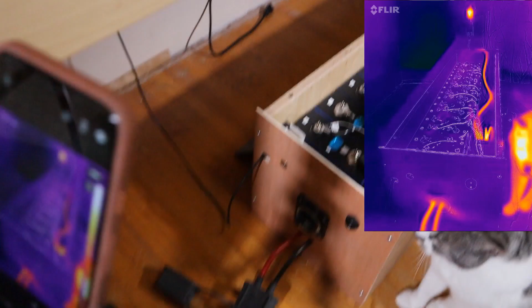Absolutely nothing. Absolutely nothing on the flexible bus bars. So as far as I'm concerned, this settles it: flexible bus bars are better than rigid. If only because, as you saw with the rigid bus bars, there were a couple of hot spots. I'm assuming because the metal plate wasn't sitting properly on top of the bus terminal, generating a little bit of heat. With the flexible bus bars, I'm able to wrench it down, and that's going to sit the ring terminal right over top and make a good connection with the top of the battery terminal. That's all I can think of.